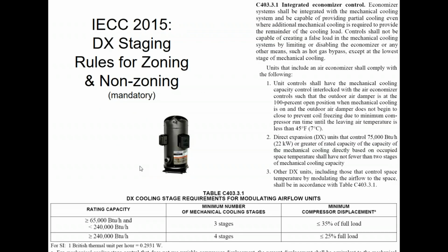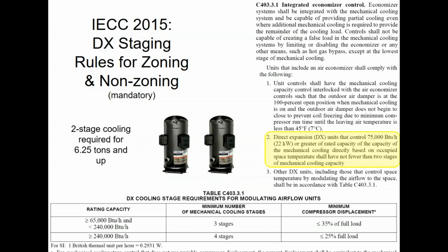All right, what else is required from a control perspective? I said we're going to come back to that integrated economizer section of the IECC 2015, and here we are back at that section. We talked about number 1. Now number 2 and number 3 come into play. Number 2 basically says that if you're going to have more than 75,000 BTUs of cooling, you must have at least 2 stages of mechanical cooling. And read up at the top, hot gas bypass is not really considered a stage. You kind of need 2 compressors, or 1 compressor with 2 stages, or a variable speed compressor, or digital scroll, or something like that.